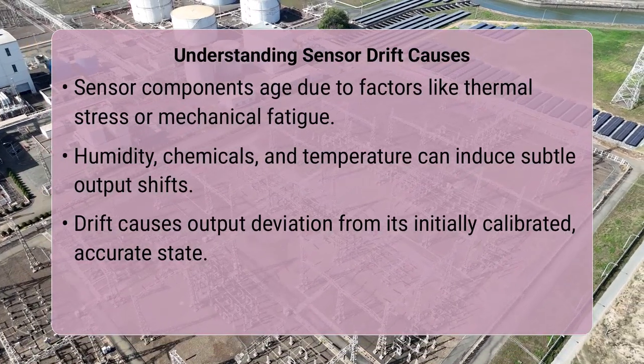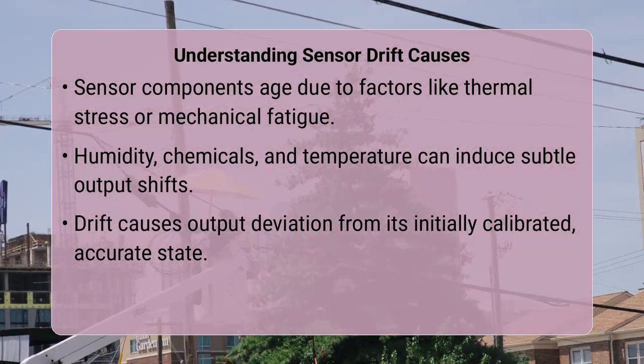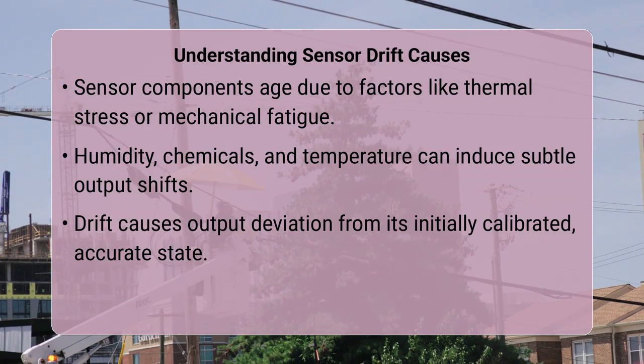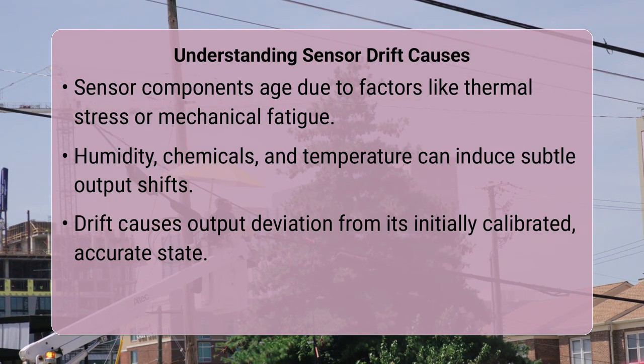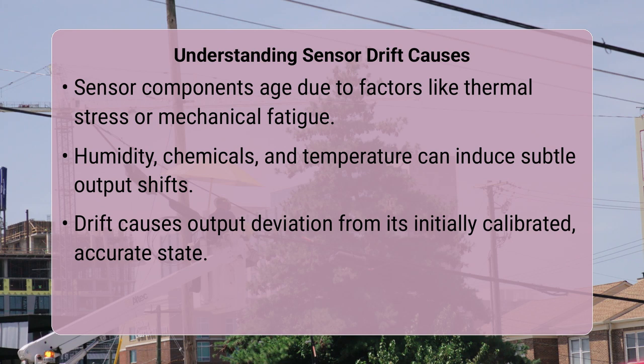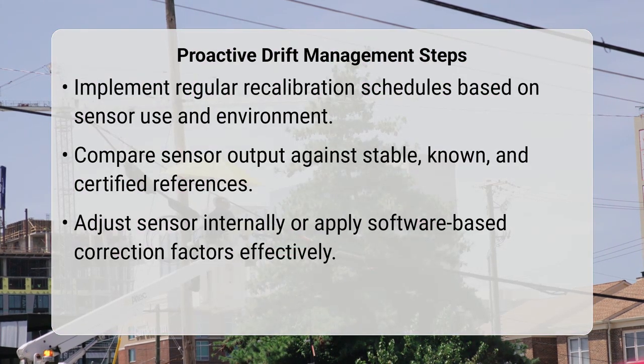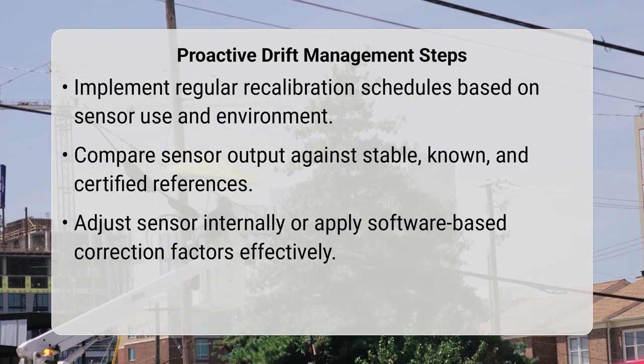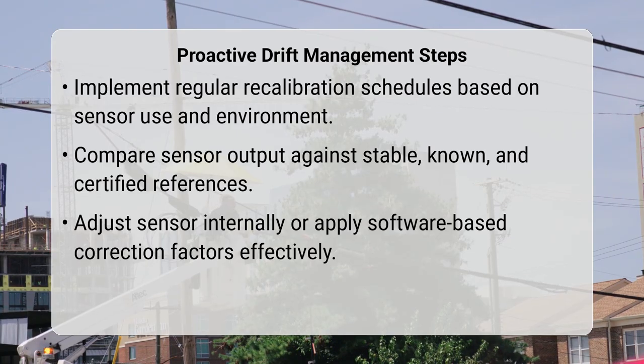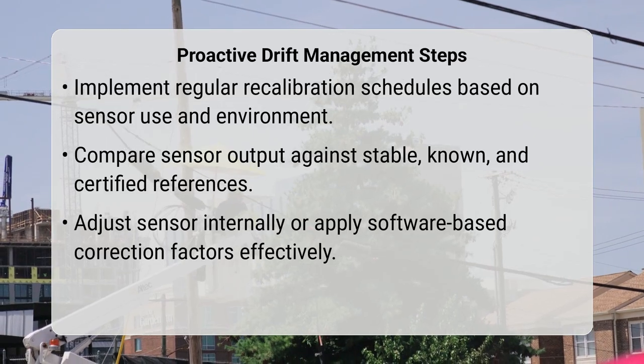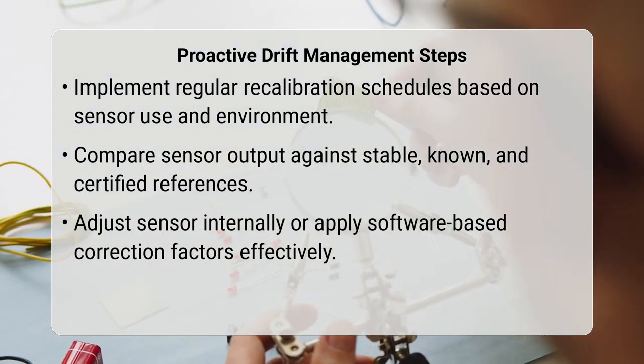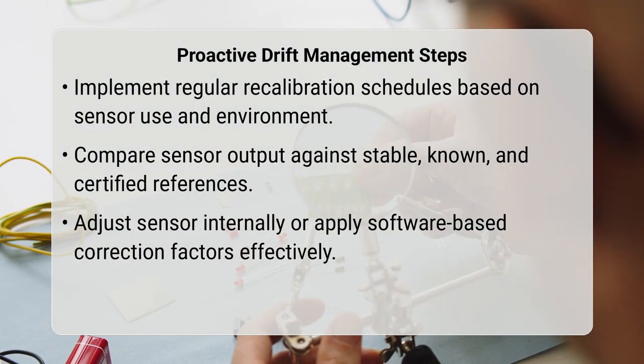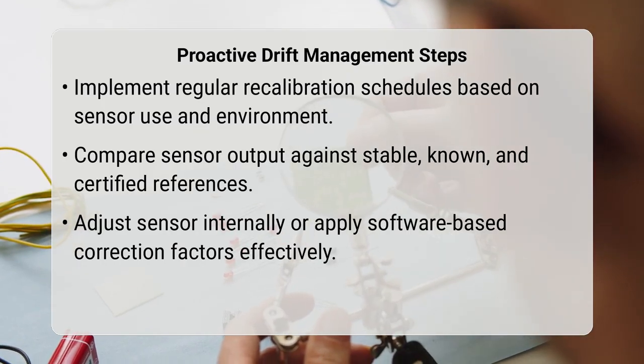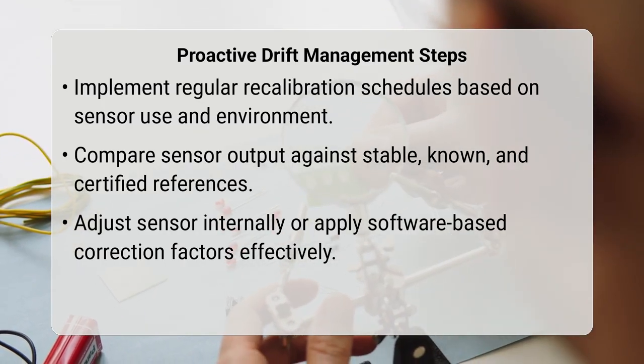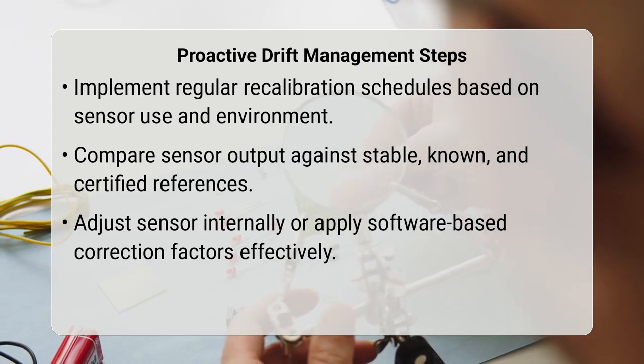Practically, managing sensor drift involves establishing a regular recalibration schedule for each individual sensor. This schedule is typically determined by the sensor type itself, the severity of its operating environment, and the specific accuracy requirements of the application. During the recalibration process, the sensor's current output is meticulously compared against known, highly stable reference standards. Any observed deviation, which signifies drift, is then precisely quantified.